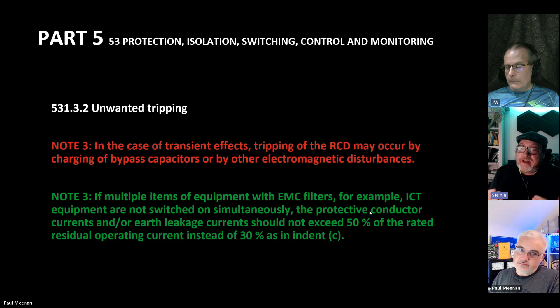But as you say, it's something that on paper we can make some guesstimations on. But for ordinary users using socket outlet circuits, it's basically a shot in the dark, really. You've got no idea what they could plug in. Even if it's the same type of equipment, one laptop power supply might not be the same as another one. Exactly, and we had to do a little bit of diversity with this. So we'd say, okay, most users would probably have tablets or Chromebooks, which would be up to maybe 0.25 milliamps leakage at best, whilst my power laptop is like 3.5 to 5, but no one really goes to the library to do gaming. They just go there to do browsing activities. And we had these conversations in the calculations, because when you have to do a design, you have to get it through assessing.